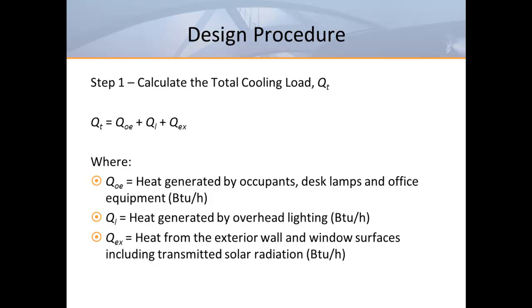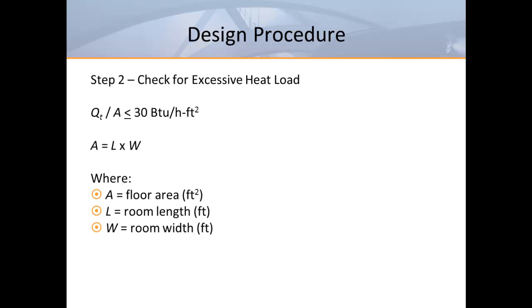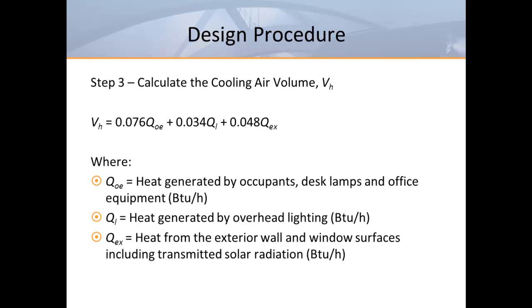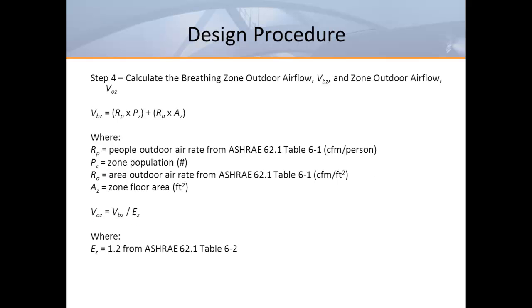Now let's look at a design procedure for displacement. First we must determine the total cooling load, then check to see if the total cooling load doesn't exceed 30 BTUs per hour per square foot. Next we must calculate the cooling volume that will need to handle the actual heat loads in the occupied zone, based on ASHRAE Research Project 949. Then we go into ASHRAE 62.1 territory — we calculate the minimum fresh air requirement for the breathing zone and apply an air change effectiveness factor of 1.2 for displacement.